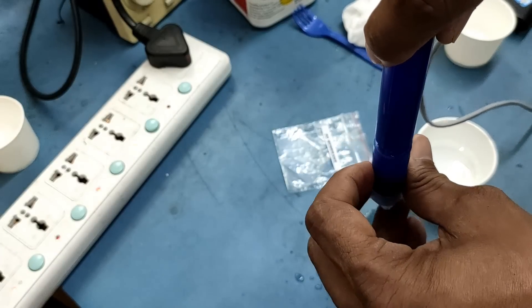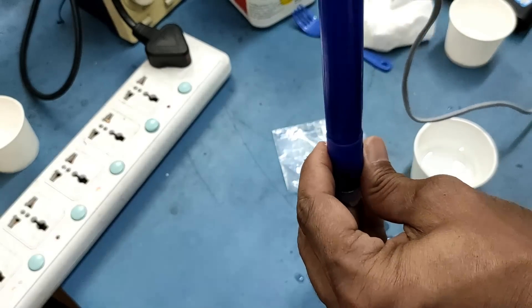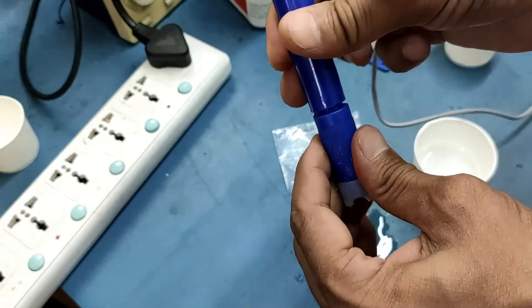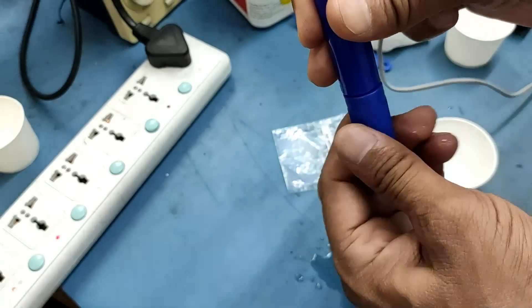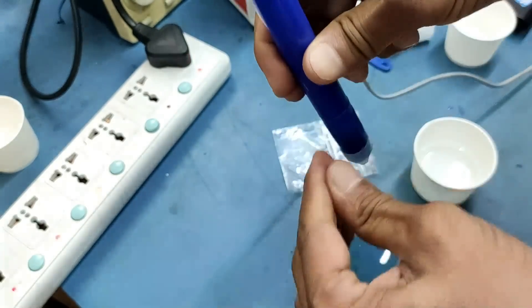Presence of any other salt in the electrolyte solution may damage the probe. The electrode tube should not contain any air bubble. If it is present, it will cause fluctuations in the readings.